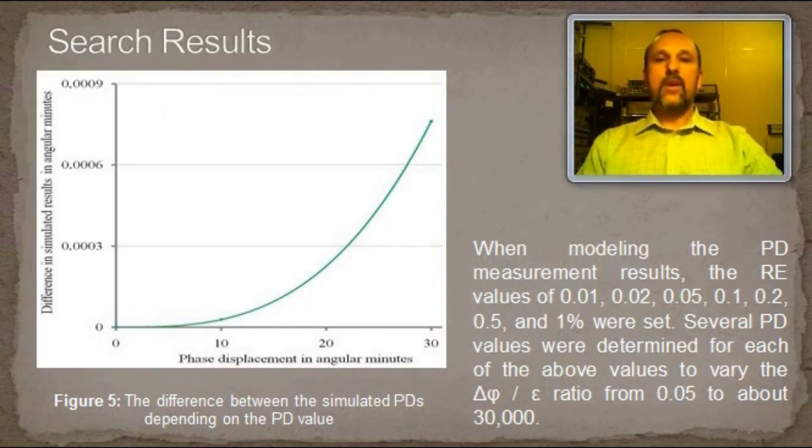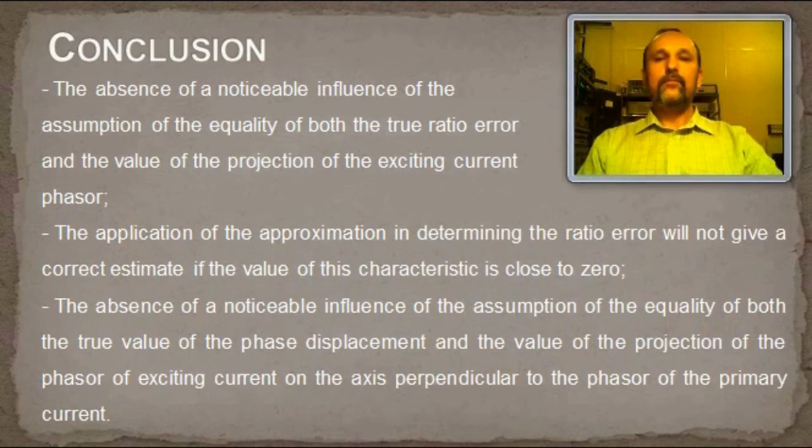Thus, the approximation in the measurement of the phase displacement does not distort the results obtained for the current transformer with errors corresponding to the accuracy class of 0.5. In assessing the correctness of the application of the approximation in determining the errors of the current transformer, it has been fixed the absence of a noticeable influence of the assumption of the equality of both the true ratio error and the value of the projection of the exciting current phasor.